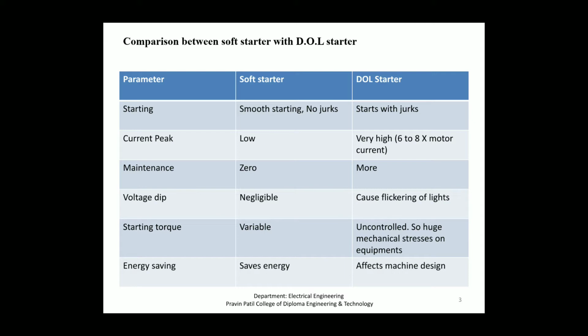Normally, suppose your current is 10 ampere, then your starting current is approximately 50 to 60 ampere at the time of starting. Then maintenance of soft starter is zero, because it's an electronic starter, but DOL starter needs more. Voltage dip is negligible in soft starter, but DOL starter causes flickering of lights. Then starting torque: in soft starter we can vary the starting torque, but in DOL starter it is uncontrolled, so there is huge mechanical stress on equipment. Energy saving, a more important point.